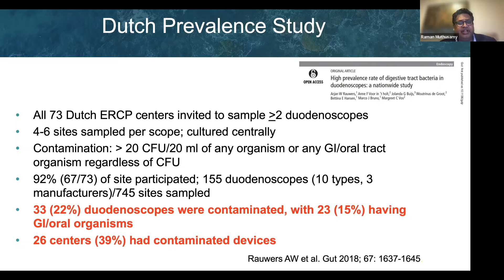And about 40% of centers had at least one contaminated device. So again, a pretty substantial number. Now, as we know, this is the reprocessing cycle we currently use, high-level disinfection. Every time you see a blue arrow, it's a step. Every time you see a green arrow, it's for something to go wrong, and each of the things next to the green arrow are what it could be.